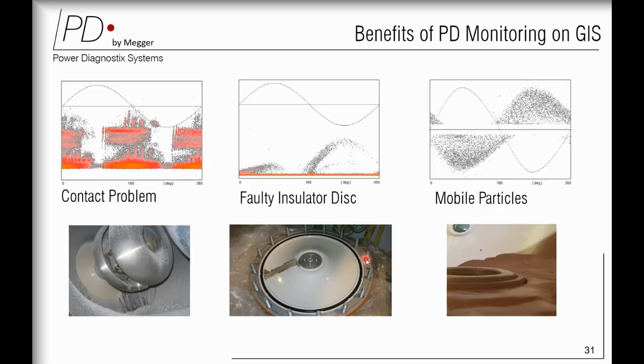Now, what are the benefits of a PD monitoring system in GIS? First, it captures any defect or impurity present in your GIS. That means poor quality of material, poor workmanship, poor design, anything will be detected with your PD monitoring system. These are a few images. This is the image of a contact problem. It was creating partial discharge, and you can see this white powder formed, because whenever you have PD there is a very high chance you get a white powder. So you have a contact problem. This is the PRPD pattern for the contact problem.